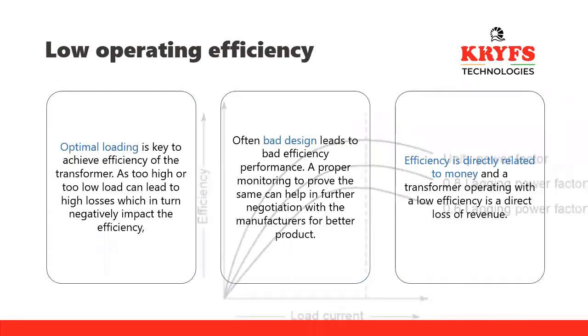Low operating efficiency. Optimal loading is key to achieving efficiency of the transformer, as too high or too low a load can lead to high losses, which in turn negatively impact the efficiency. Often bad design leads to bad efficiency performance. Proper monitoring to prove the same can help in further negotiation with the manufacturer for a better product. Efficiency is directly related to money, and a transformer operating with low efficiency is a direct loss of revenue.